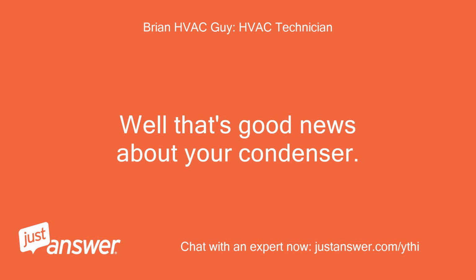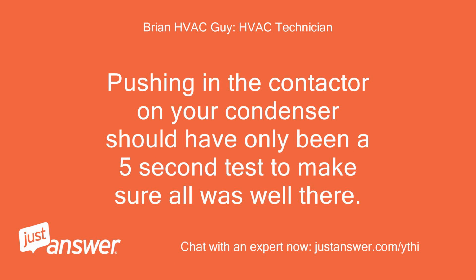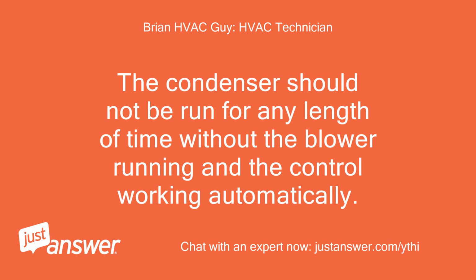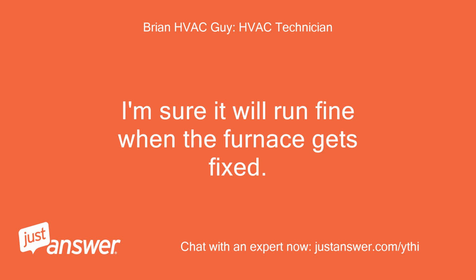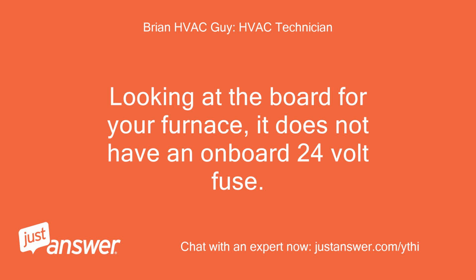Well, that's good news about your condenser. Pushing in the contactor on your condenser should have only been a 5 second test to make sure all was well there. The condenser should not be run for any length of time without the blower running and the control working automatically. I'm sure it will run fine when the furnace gets fixed. Looking at the board for your furnace, it does not have an onboard 24-volt fuse.